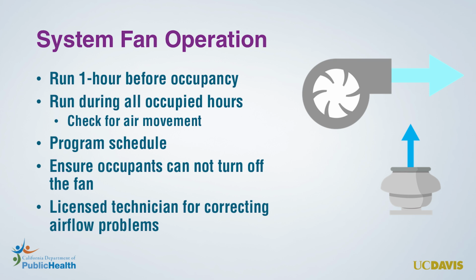First, you'll want to make sure supply fans and exhaust fans are running at least 1 hour before scheduled occupancy and during all occupied hours, including when janitorial staff are working, to make sure ventilation and filtration are continuously being delivered to the space. The fan should be running all the time regardless of the heating or cooling status.